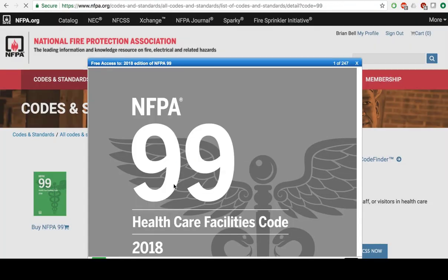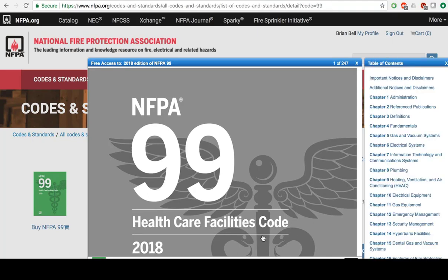The best way to navigate these codes online is to use the table of contents. Typically, the chapters we are going to be interested in are Chapter 6, Electrical Systems, and Chapter 10, Electrical Equipment. Electrical Systems has codes and regulations related to outlets, isolated systems, and generators.